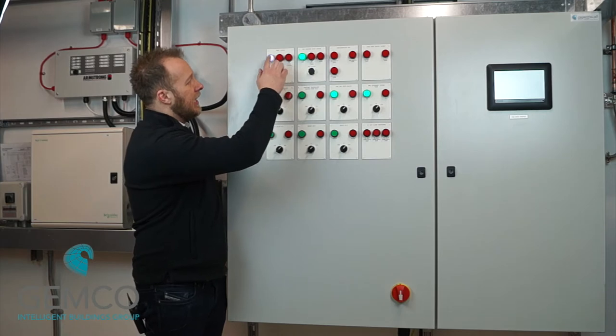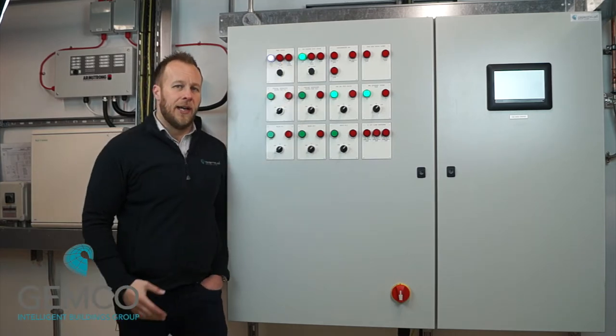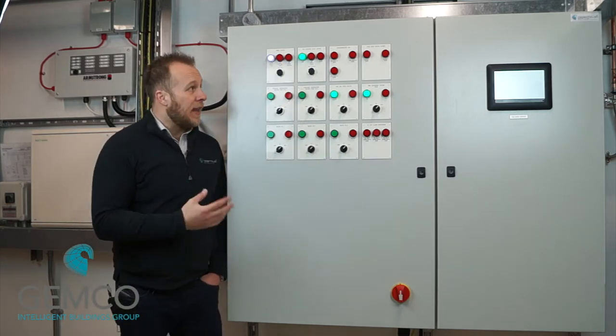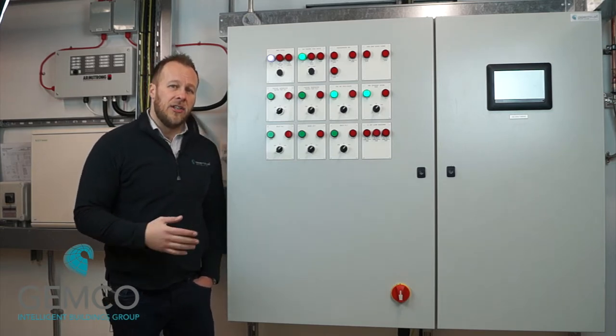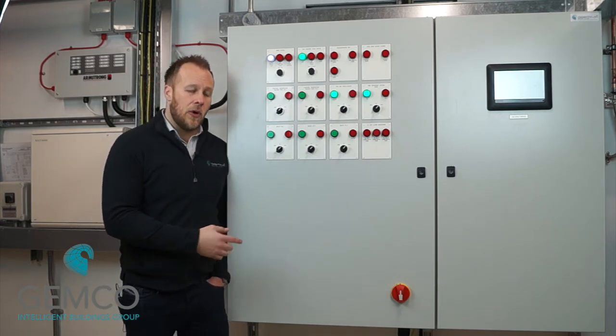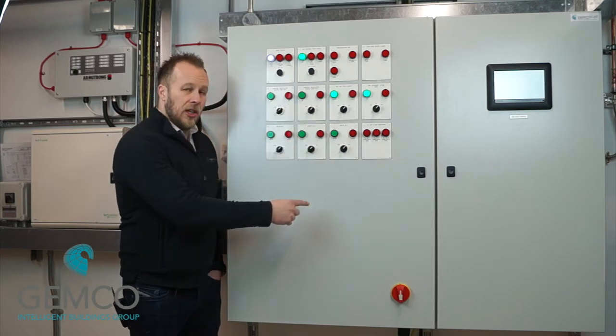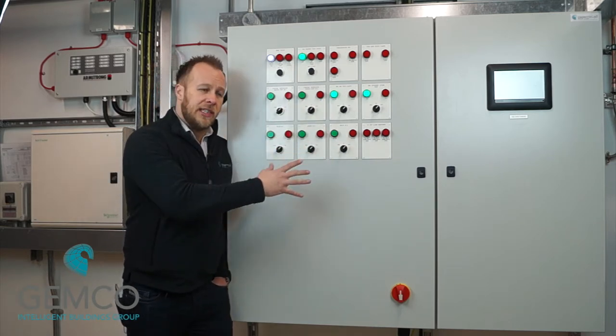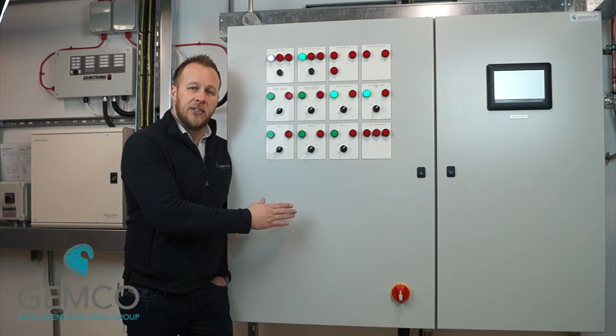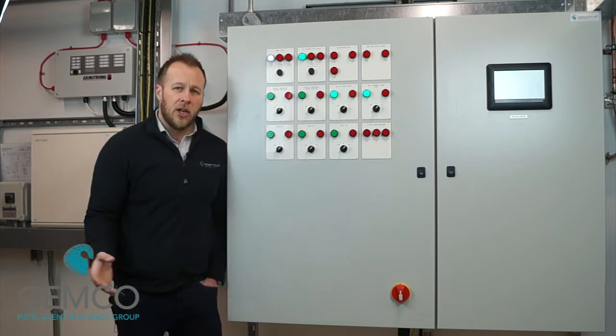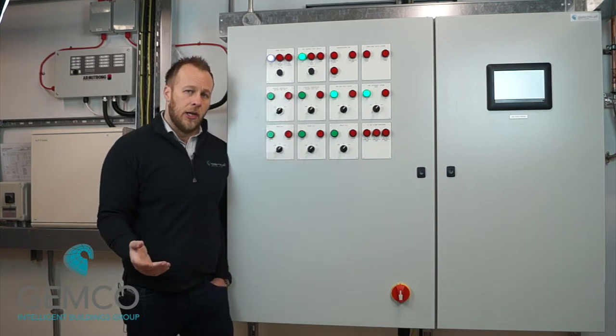The first light is the control circuit live lamp. Now that should always be lit. If that isn't lit, then the chances are that you've got a control circuit fault. And the control circuit is the 24 volt control circuit that serves the entire circuitry inside this control panel. So if that light is out, chances are you're not going to have any plant running.